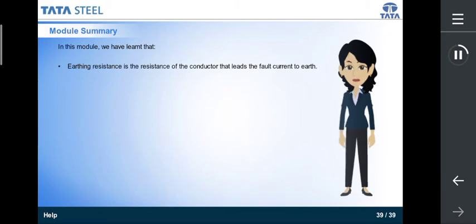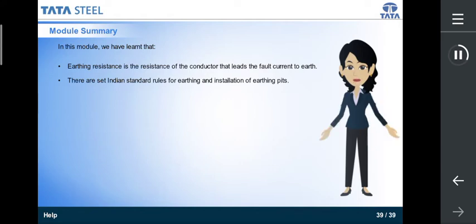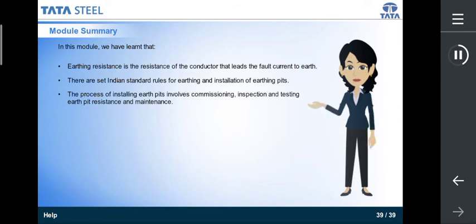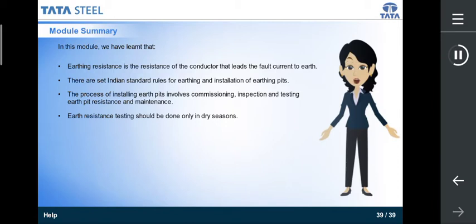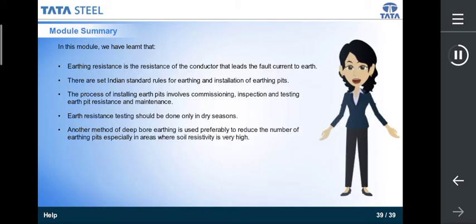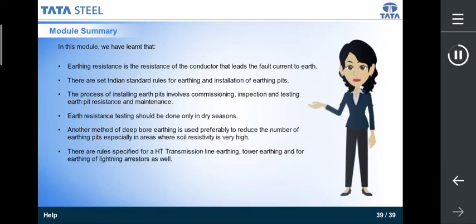In this module, we have learned that earthing resistance is the resistance of the conductor that leads the fault current to earth. There are set Indian standard rules for earthing and installation of earthing pits. The process of installing earth pits involves commissioning, inspection, testing of earth pit resistance, and maintenance. Earth resistance testing should be done only in dry seasons. Another method, deep bore earthing, is used preferably to reduce the number of earthing pits, especially in areas where soil resistivity is very high. There are rules specified for HT transmission line earthing, tower earthing, and for earthing of lightning arresters as well.